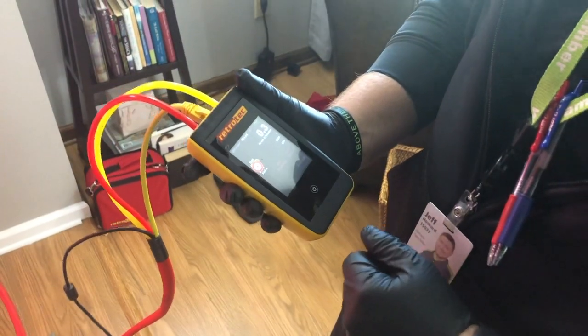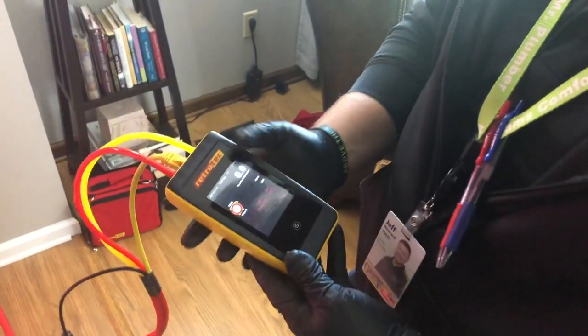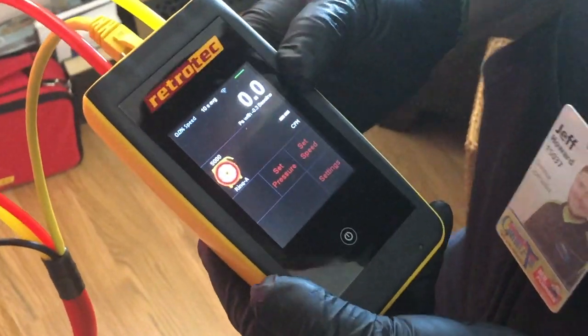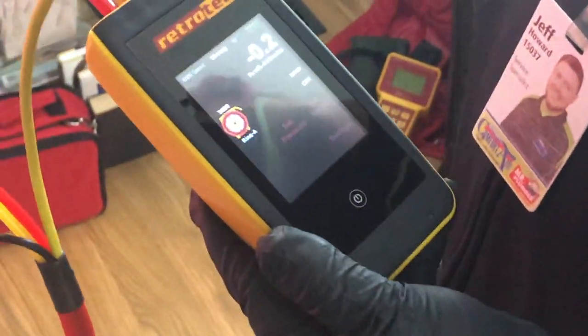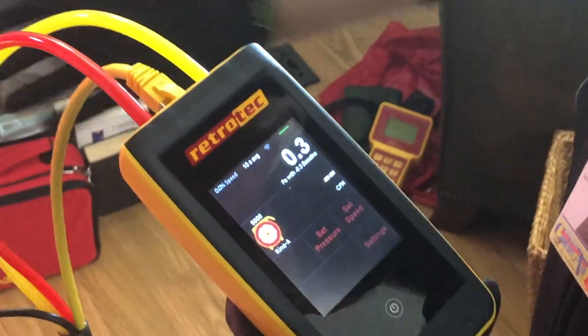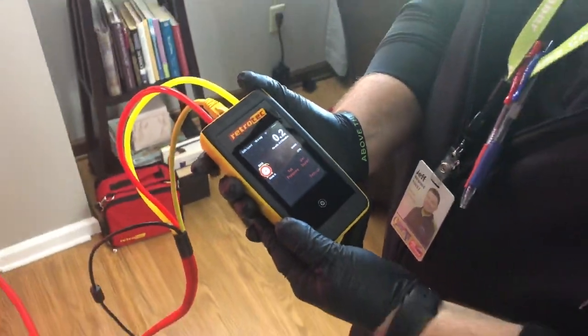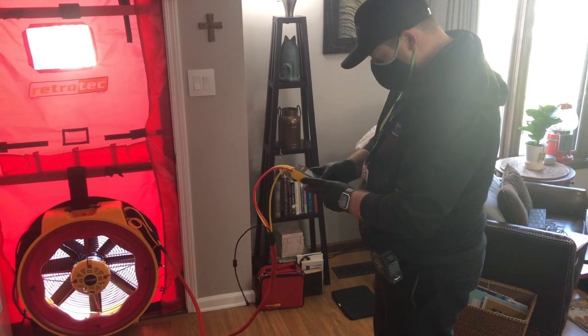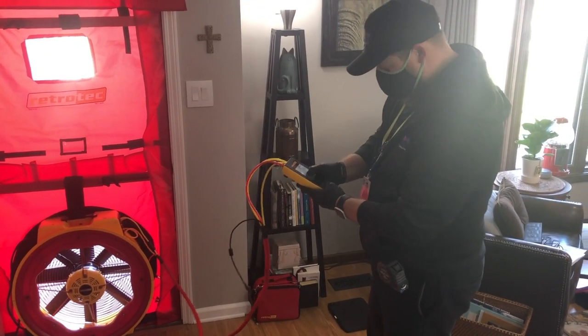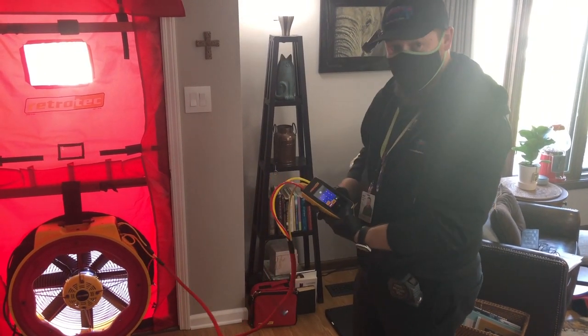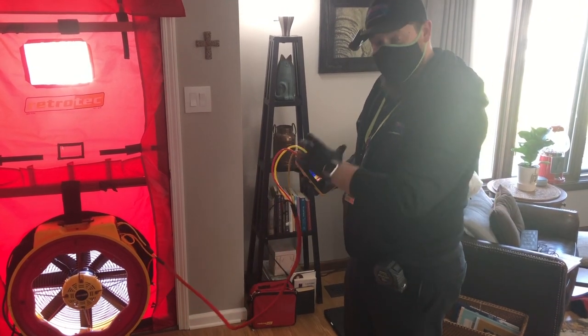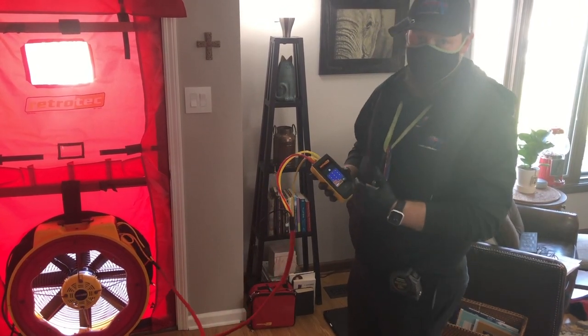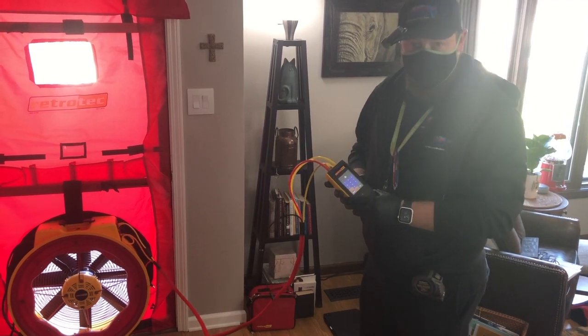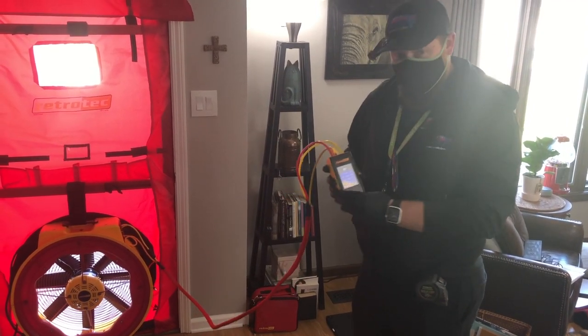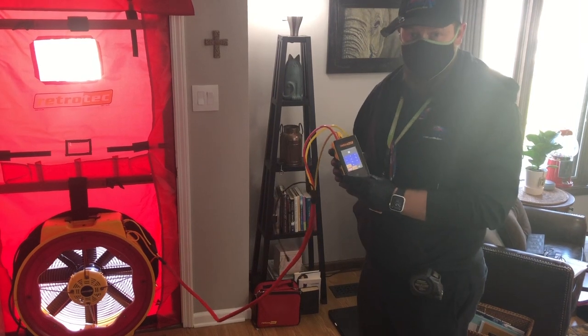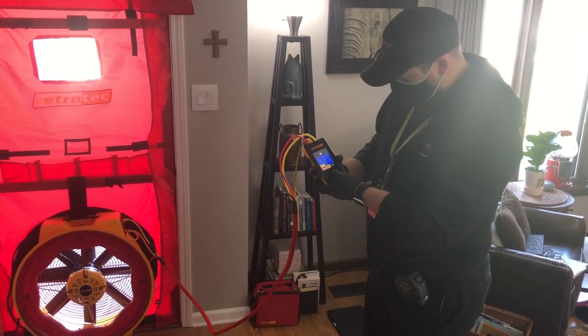So what we do before we actually get the blower door started is we will go through and do a baseline. What the baseline is going to tell us is the pressure that's outside, the wind that's attributing to our fan today. So now we're actually going to go ahead and set our pressure to 50 pascals, and what we're doing with that is depressurizing the house. So we're putting the house in a negative state so we can expose everything that's infiltrating into the home. 50 pascals is a typical number that we want to pressurize or depressurize a house at. So here we go.